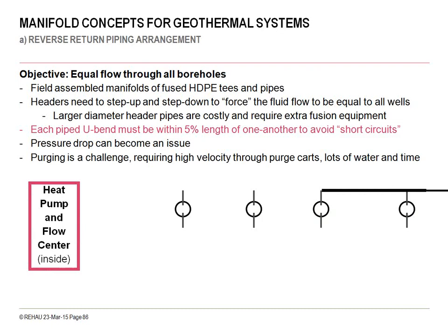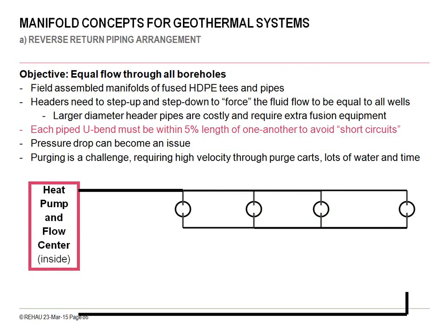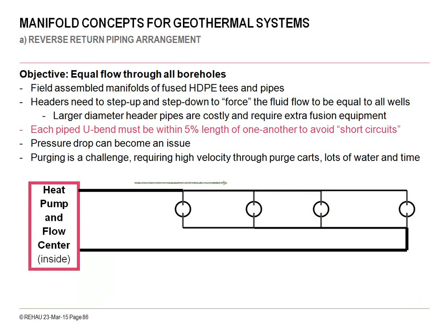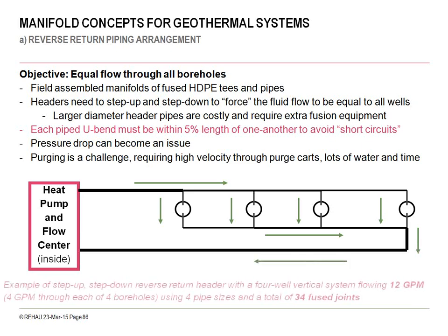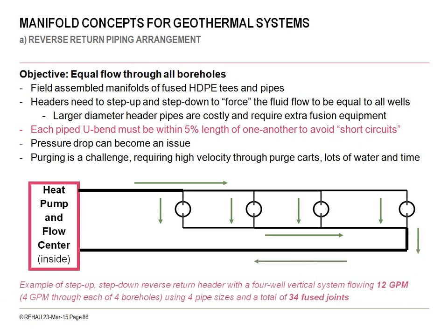With the high-density polyethylene, typically the boreholes are tied together, if you will, with horizontal piping in what's known as a reverse return headering pattern, meaning you can see here the first borehole on the left. You can see that the return from the heat pump going back out to the field is the first into that borehole, and then the supply to the heat pump coming out is the last in. So it's first in, last out, second in, third to last out, etc.